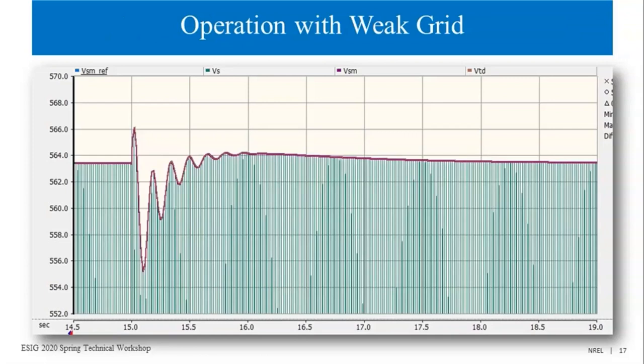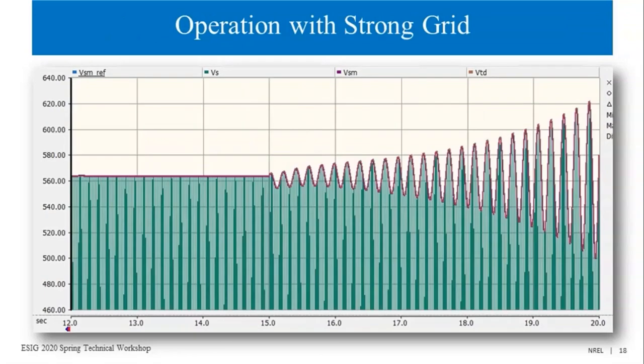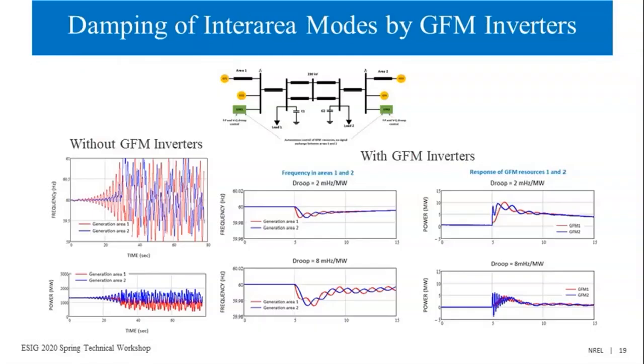But if the short circuit ratio becomes higher, and we connect it to a strong grid, it has a stability problem. So this is a little counterintuitive, but it shows that grid forming resources will have a different kind of stability challenges. They like weaker grids because they are voltage sources. So they don't want to connect to a strong voltage source like a strong grid. They need some high impedance from the grid. So as we move more and more towards grid forming resources, we might see that instead of weak grid problems, we may start talking about strong grid problems.